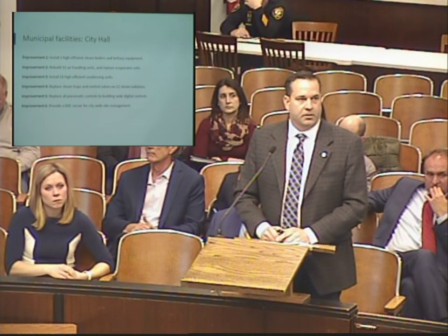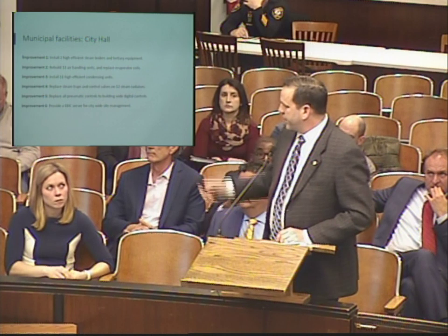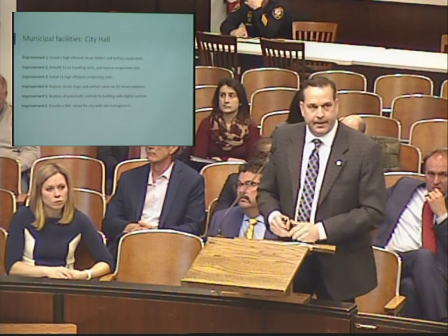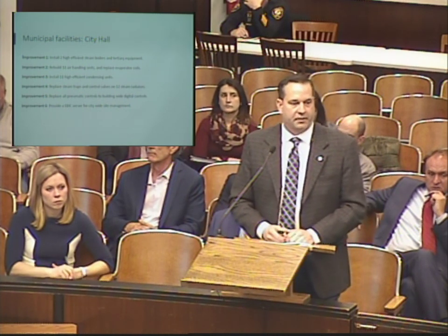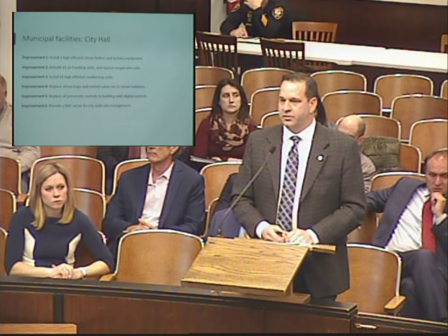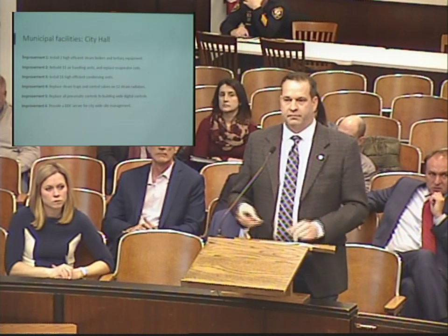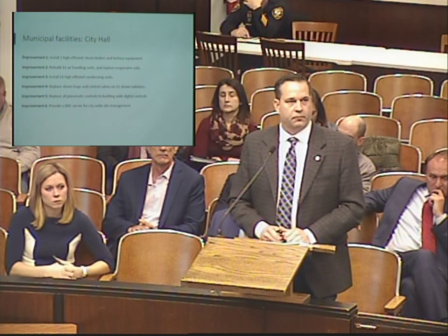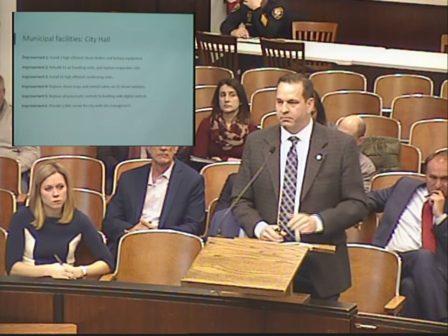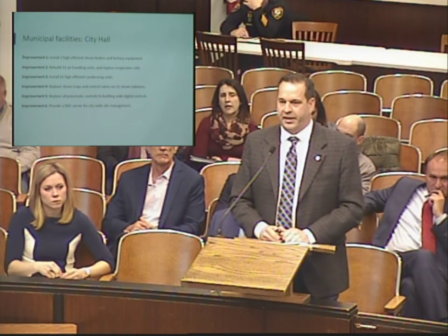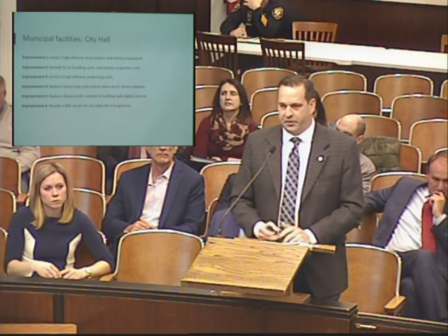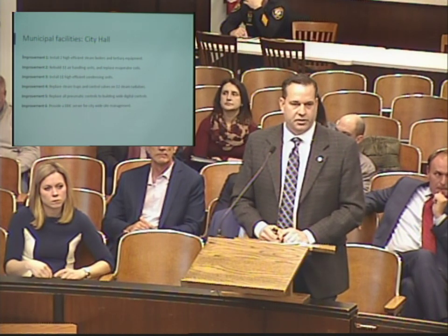Throughout the areas, I believe up here in council chambers and down on the first floor, we have various radiators. They're just steam radiators that have a control valve and a trap. We're going to replace the traps. Are probably mostly all failed. They're tucked away, out of sight, out of mind, and when they fail, people really don't know it. And that's a huge inefficiency.